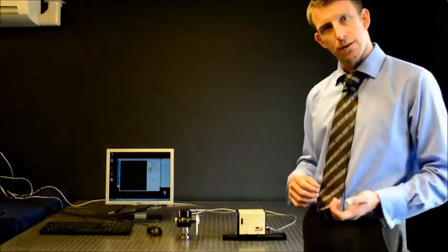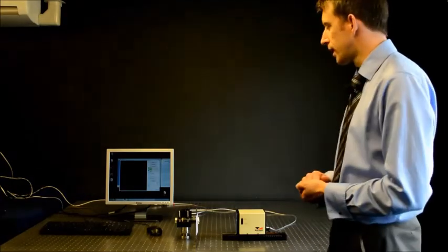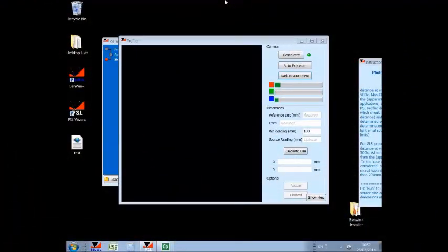We will now look at this through the software simulation to look at the calculations. Now we will repeat the entire procedure using software simulation to demonstrate the operation of the PSL Profiler. I have positioned the PSL Profiler to 100 millimeters on the optical rail. I have measured out 200 millimeters from the front face, and at that location position my alignment aid.